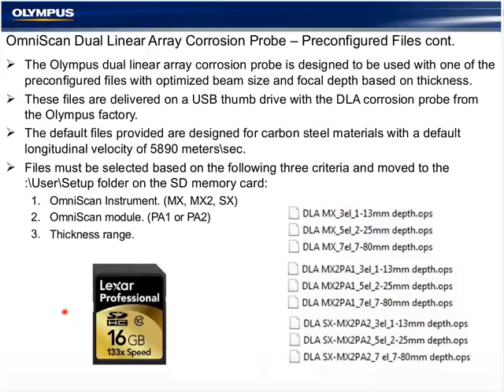With the probe from the factory comes a USB flash card for files to be transferred to the user folder of your SD memory card. The corrosion probe is designed to be used with one of these pre-configured files for optimized beam size and focal depth based on thickness. The default files provided are designed for carbon steel materials with a default velocity of 5890 meters per second. Other velocities or other types of materials are compatible with the probe and the OmniScan, and that's explained a little bit later. But the overwhelming majority of these applications are carbon steel. That's changing rapidly, but even today it's overwhelmingly carbon steel.